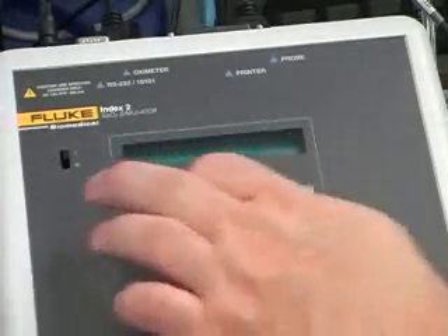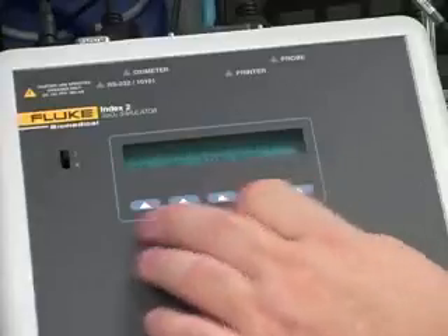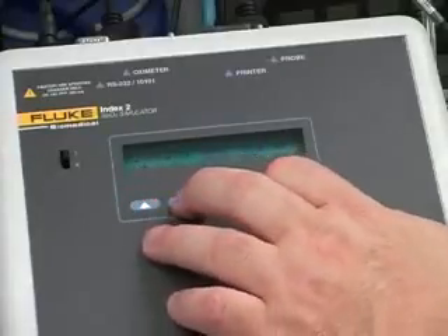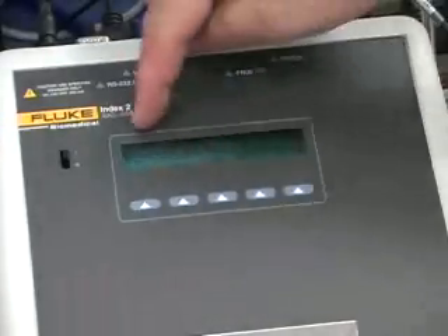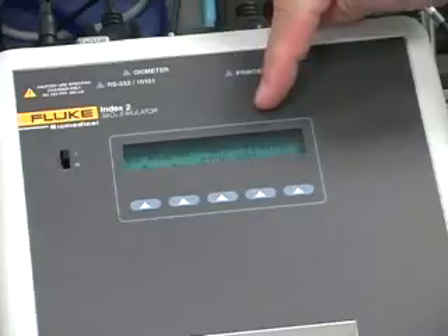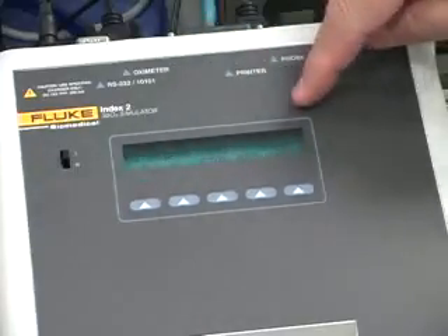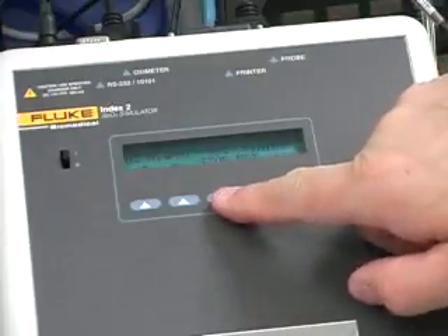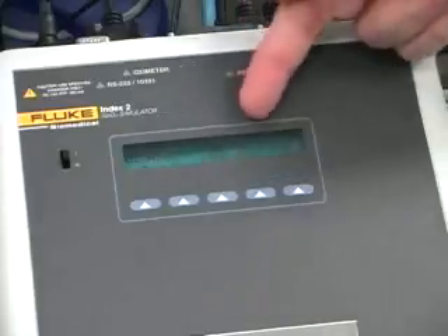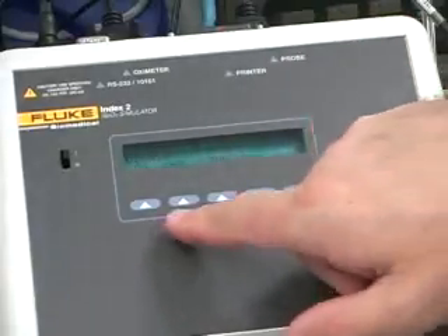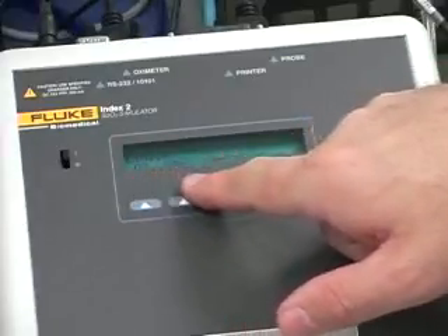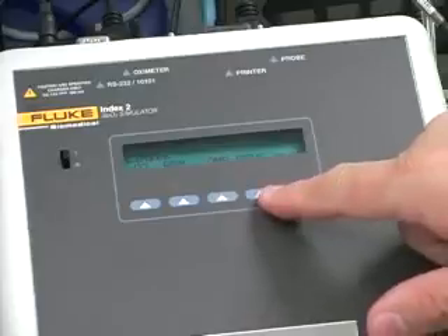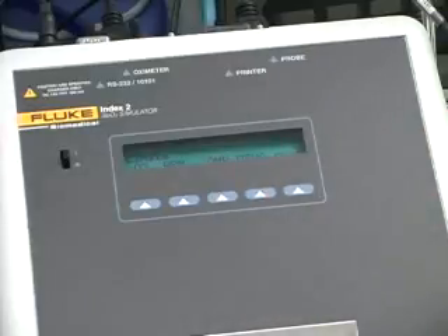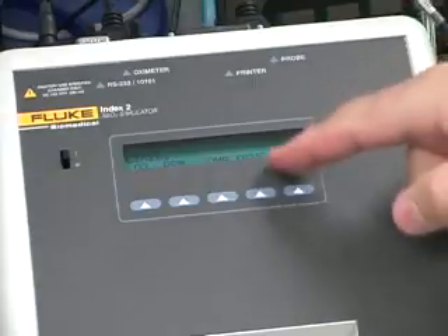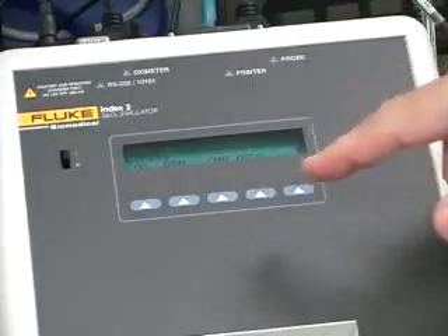So basically, you can go through. You can start a test, and then go in and change it. You wait and see how long it takes for the system to catch up and make a measurement. Once it makes a measurement to 98, which it now has, you can push that, and that will give you the response. So that is basically for those tests. You can run oxygen saturation rate, pulse amplitude, and also an asystole type alarm. When you have a measurement and you've got the alarm set, you can test having the patient actually go into an asystole condition.